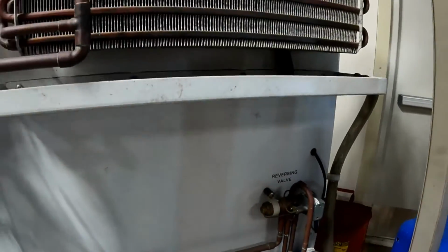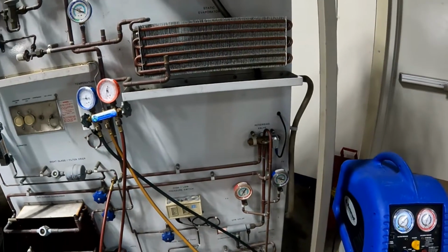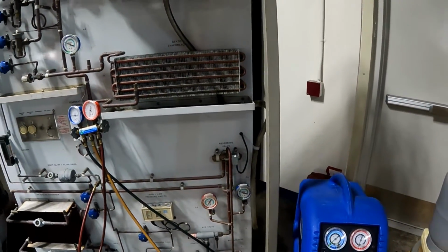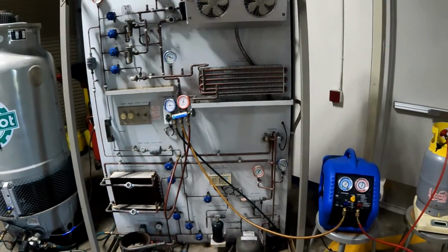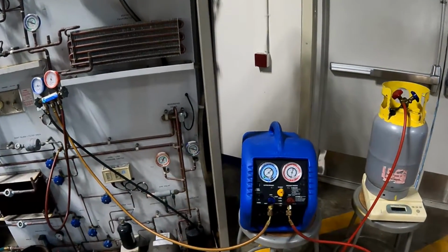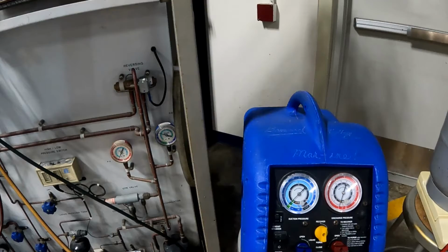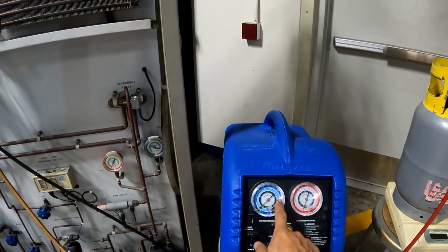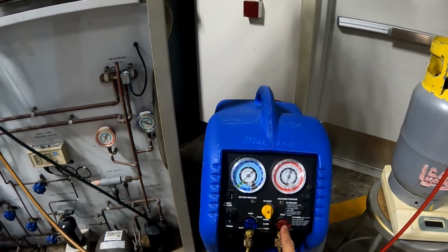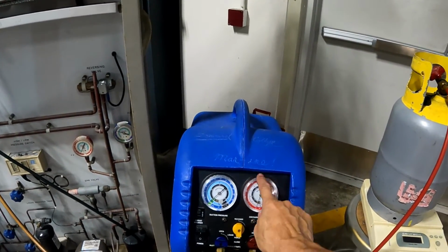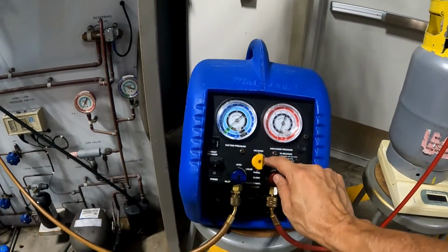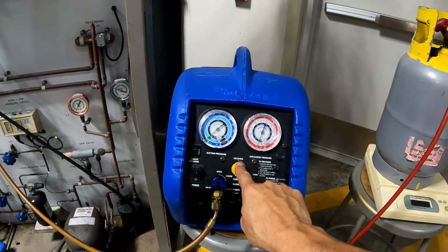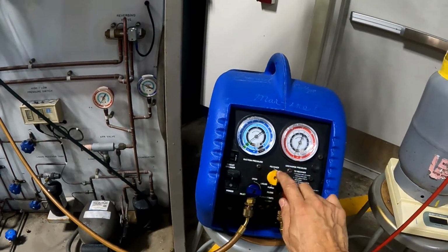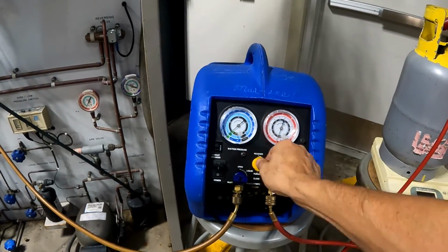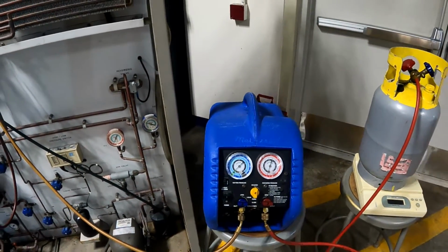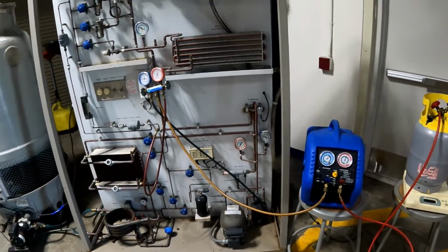the equipment. Okay, right now we are going to recover that small amount of refrigerant, and after that we are going to do the vacuum. We are going to recover with our machine. Remember that the machine has one input, the inlet, low pressure, with the low pressure gauge. This is the discharge, with the high pressure gauge, and this is the valve to purge or recover. In this particular case we are going to recover. At the end we are going to purge the system again, and after that we are going to charge the refrigerant again in the system.